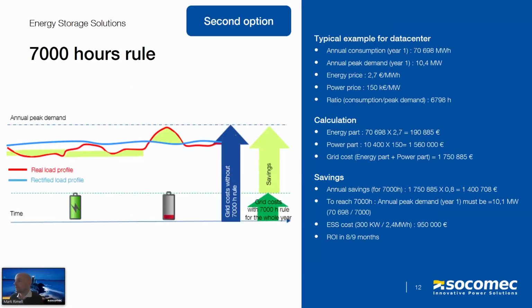So the 7,000 hour rule here, we have a typical example, this time for a data center, whose annual consumption in year 1 was 70,000 megawatt hours, with an annual peak demand in year 1 of 10.4 megawatts. We also have their energy price and power price included, but you can see their ratio is just below the criteria. They are just below 7,000 hours at 6,798, which therefore means they cannot currently benefit from the 7,000 hour rule. On this basis, their current grid costs are €1.7 million.